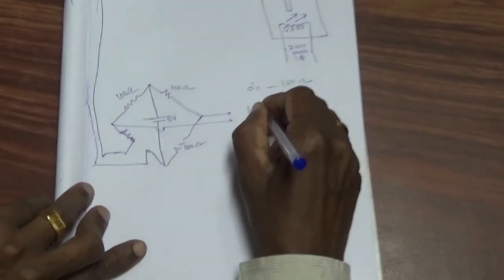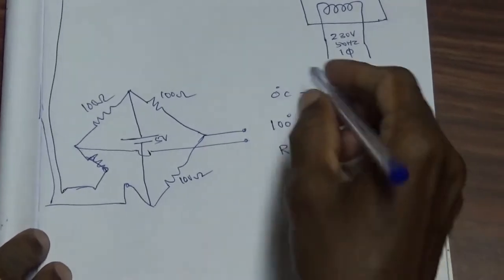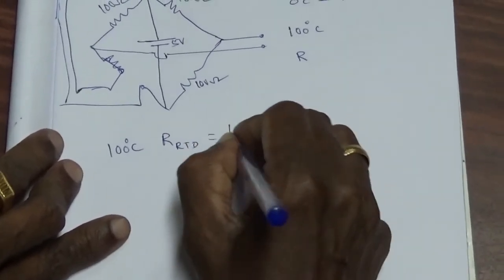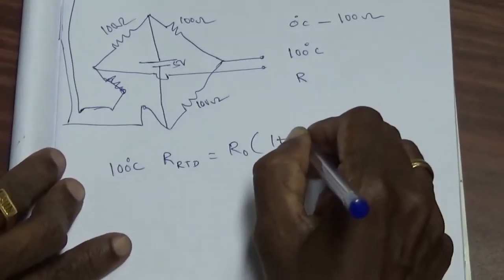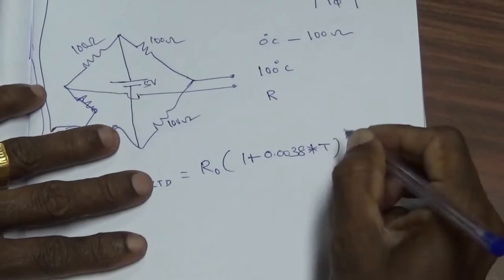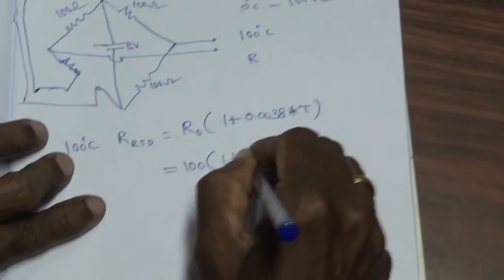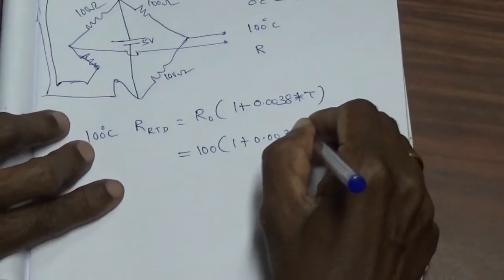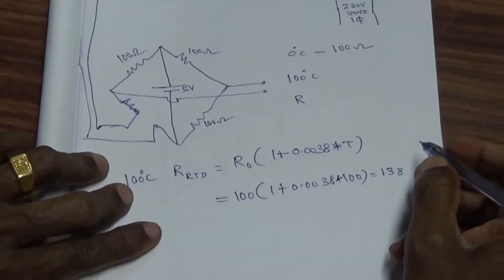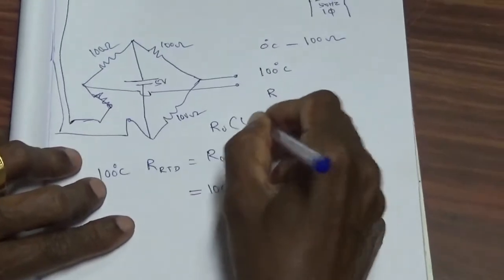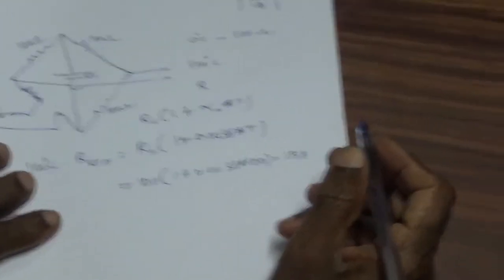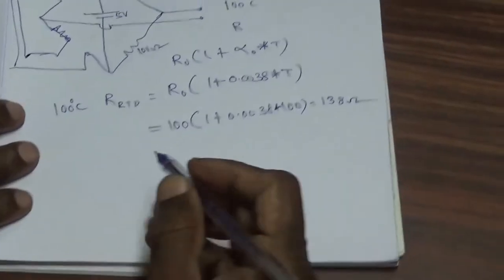At 100 degrees centigrade, the resistance of the RTD equals R₀ multiplied by (1 + 0.0038 × T). That is 100 ohms multiplied by (1 + 0.0038 × 100), which equals 138 ohms. The formula is R = R₀(1 + α₀T), where α₀ for the RTD is 0.0038, giving us 138 ohms.